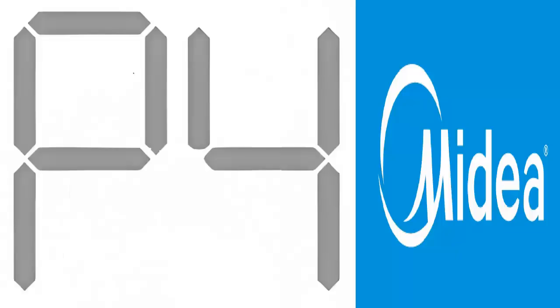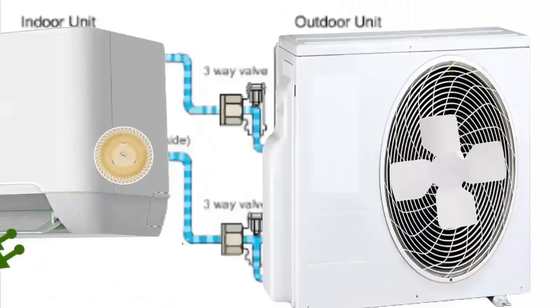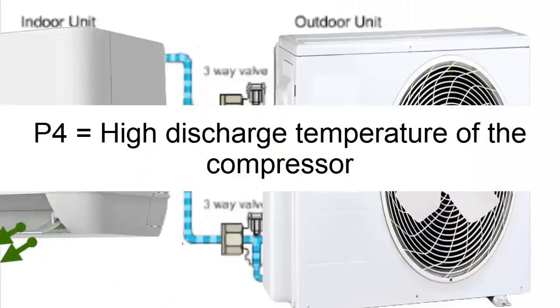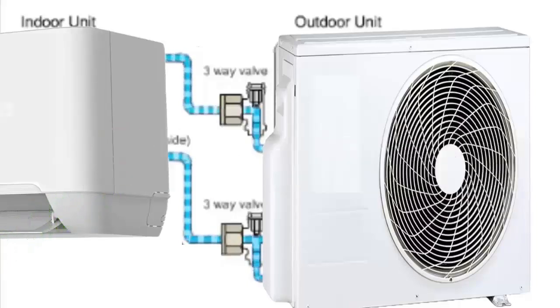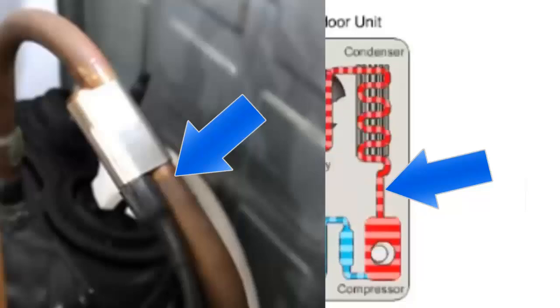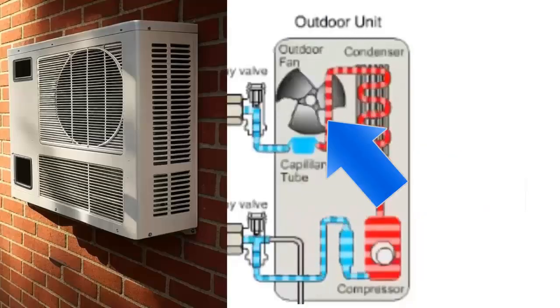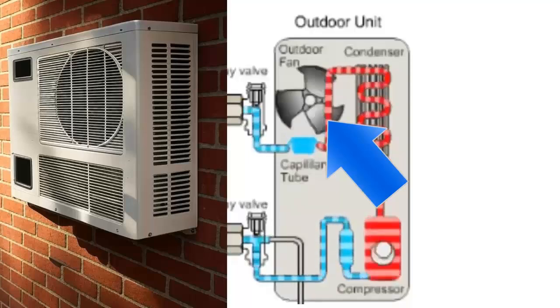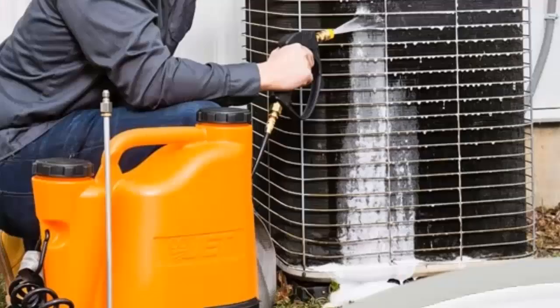However, for Midea units with HRDN series outdoor units, this code indicates high discharge temperature protection for the compressor. Recommendations: A. Make sure the outdoor unit fan is functioning correctly. B. Check the cleanliness of the outdoor unit coil.